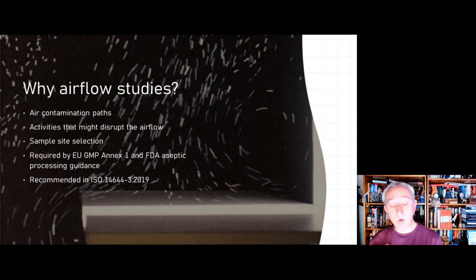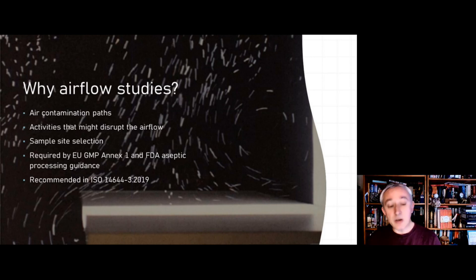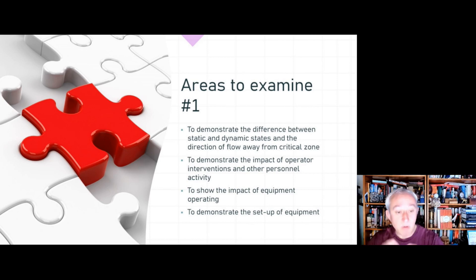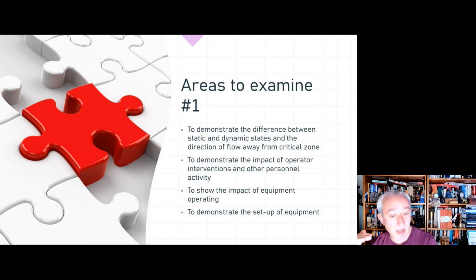The analysis of results can also be beneficial for the selection of sample sites and sample frequencies, and for understanding and refining personnel procedures and material flow into an aseptic processing area. Airflow studies are normally performed using either a smoke pencil or a smoke generator, depending on how much smoke is required, and we want to take careful note of air direction and air velocity.